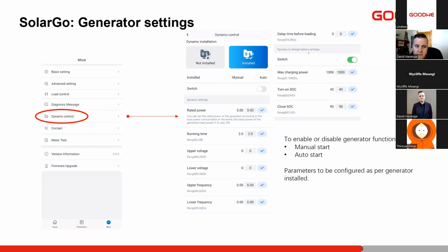And next we can do the charging switch. So to charge the batteries from the utility, from the generator, you can select the maximum charge power and the turn on and turn off SOC. So the turn on SOC will mean, if you're running in an off-grid scenario, once your batteries reach that percentage, it will automatically close the relay, which will then start the generator.